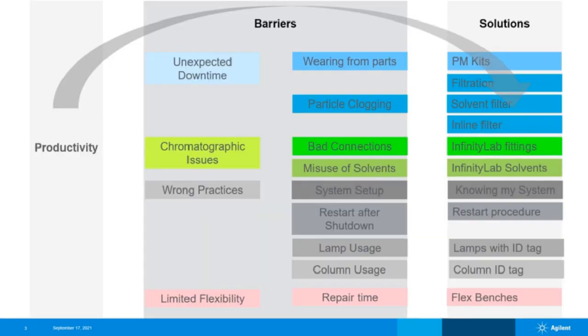Productivity is strongly affected by different barriers, and we can classify them in different categories. The unexpected downtime, generally coming from parts wearing and clogging in the flow path. The chromatographic issues, which are generally due to bad connections in the flow path or misuse of solvents. Good practices in HPLC will strongly help to reduce the most frequent barriers and will help to keep high productivity. And Agilent has definitely good solutions to overcome these barriers, and in the coming slides I will address them.